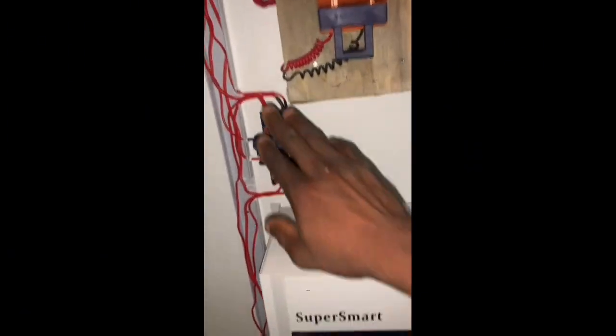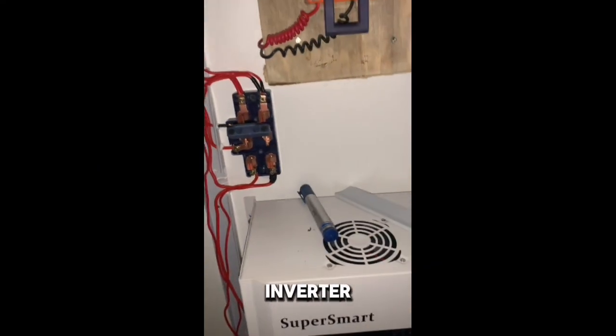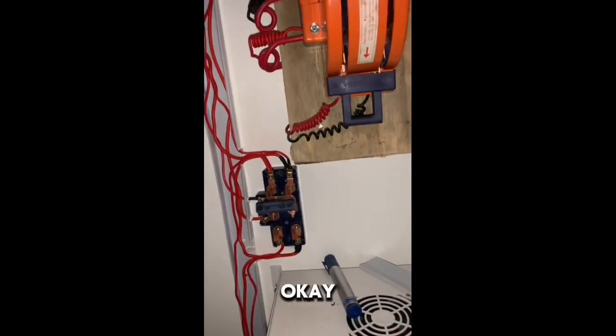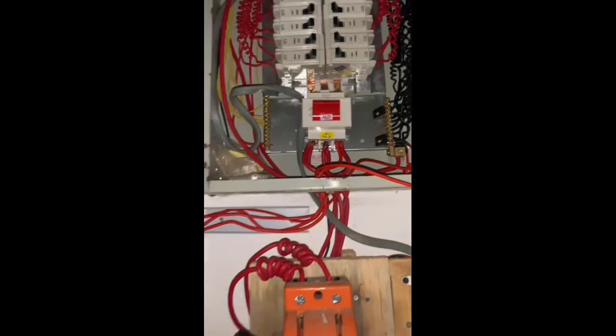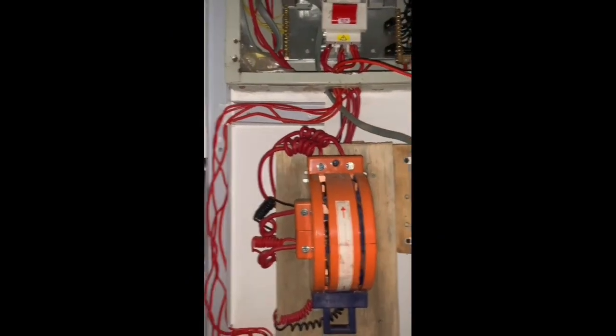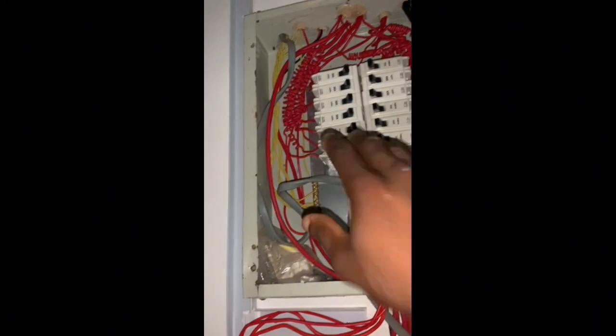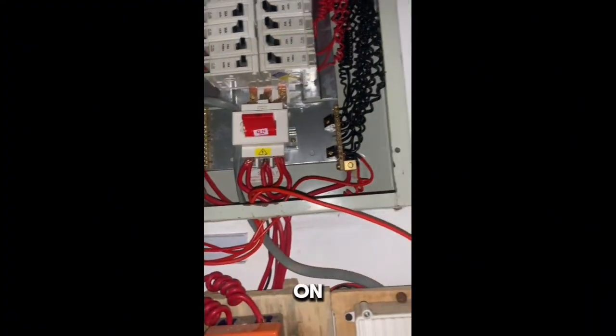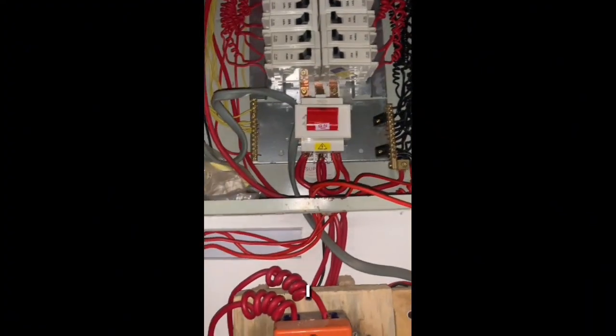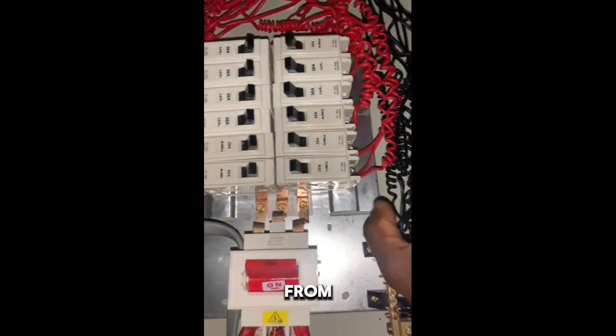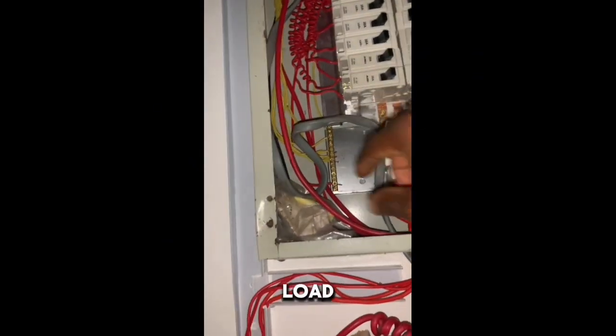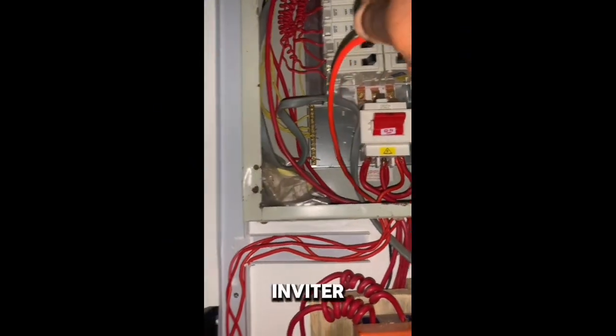All right. Right now, I'll say we're done with the connection of the bypass for the inverter. Looking at the DB, it means every other thing here remains the same. Power comes in, but the only part left now is for us to separate this load. I'll be turning on the gen shortly. Where we do that, from this breaker, we should be taking off the load that we want to be on the inverter. This is the inverter output.